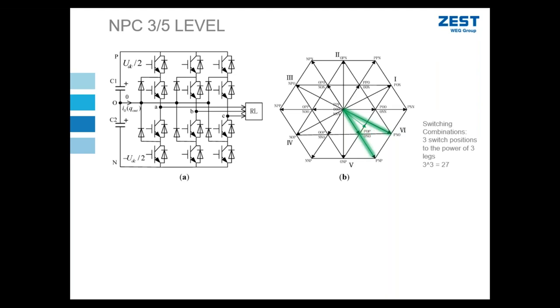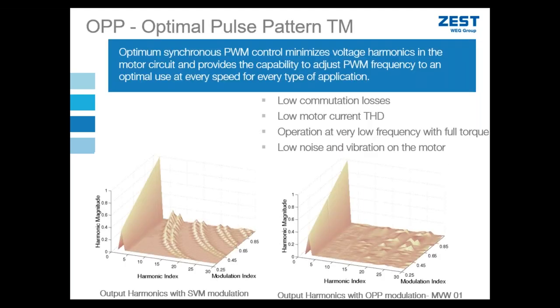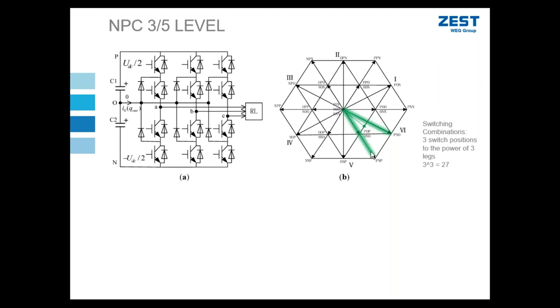And going back to the short vector, I have an additional option because I can choose which of the two short vector switching patterns I can use. Ultimately, in order to achieve the desired space vector that my motor is demanding, I need to tell my VSD which are the two best options to choose. Depending on some specific speed and voltage requirements of the motor, the selection of which of those two vectors is optimal can have a dramatic effect on the amount of harmonics that is provided to the motor.